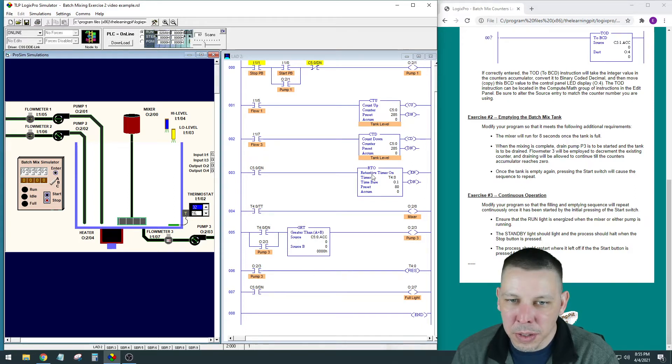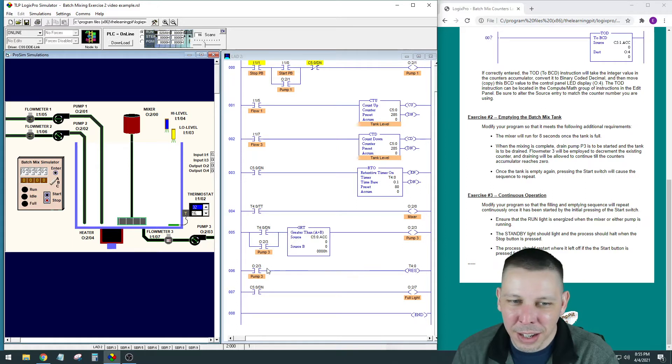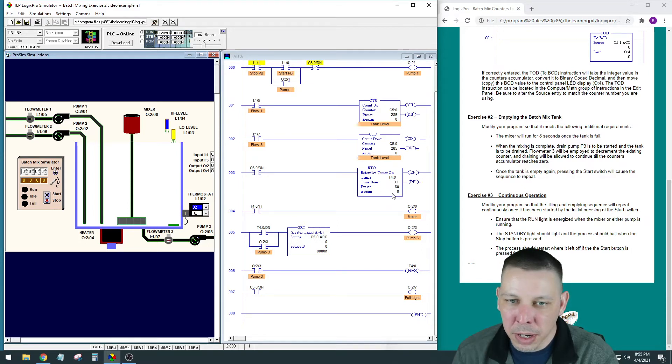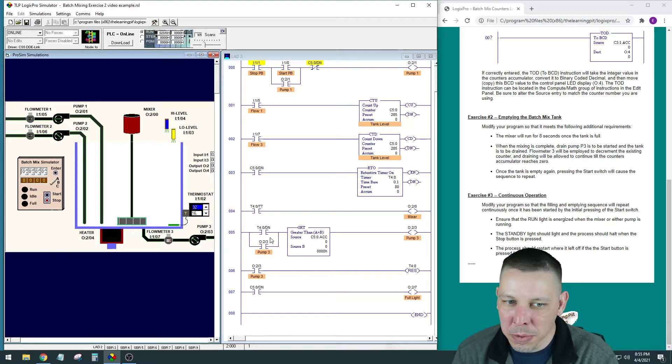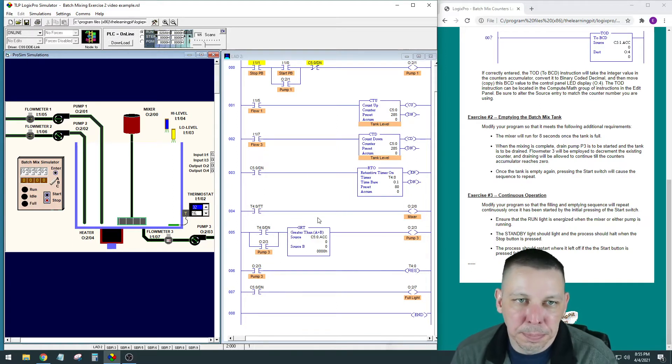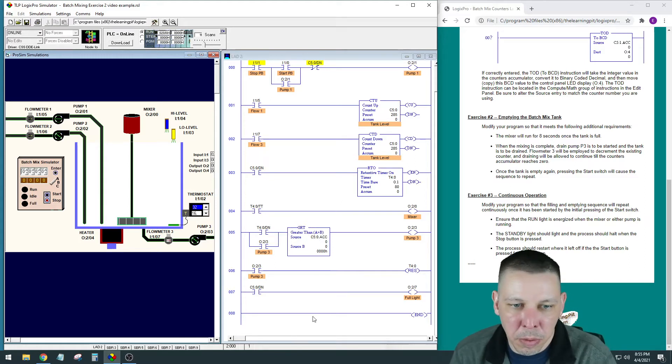It's happening very fast. T4.0 is made right here, it latches in, and then as soon as it latches in, this goes high and resets T4.0, and it's not done anymore so then this opens up. It's very fast—this changeover happens in one cycle of going through the rungs.